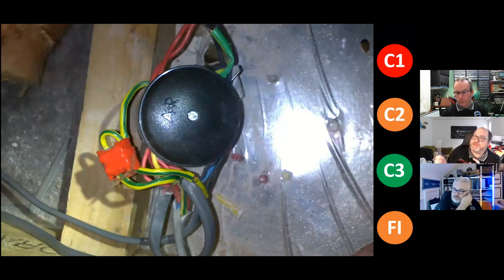I've known a few though to say, but this is in the loft space, so because you've got single insulation there, you don't have the sheathing. Is a loft space an enclosure? Because some people do think that. They think it's not readily accessible. Well, it's in a loft space. It depends on the person accessing it, isn't it? And in a domestic in particular, where the persons going up there are not authorized or skilled persons. They're home. No, they're not.